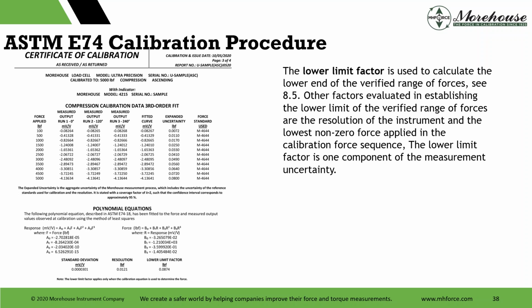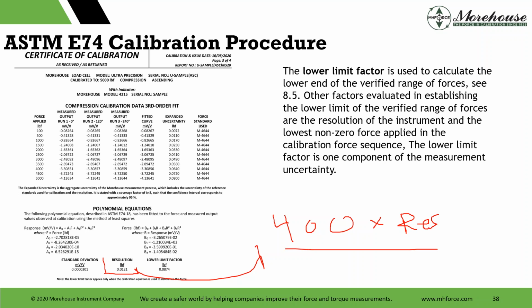So basically what I'm saying here, our resolution is 0.0121. ASTM says, hey, your first force point cannot be less than 400 times the resolution. Just can't. And 0 is not a calibrated test point. So 400 times the resolution is as low as we possibly can go. It also makes a recommendation of a 2% point. So right here, we're choosing the 2% point.